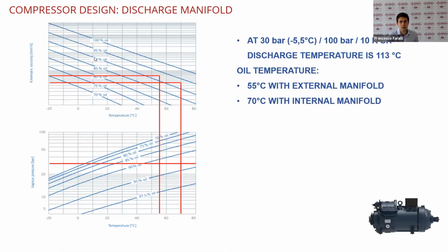Here is an example that we have made in our lab. We are working at 30 bar suction, meaning -5 Celsius, 100 bar, so it's transcritical condition. And the discharge temperature in this case is 113 degrees Celsius. What we have done is test a transcritical compressor with and without the external discharge manifold. So the oil temperature with the external manifold is 55 degrees Celsius, while with the internal manifold it is 70 degrees Celsius. So it's a 15 degree lower oil temperature.